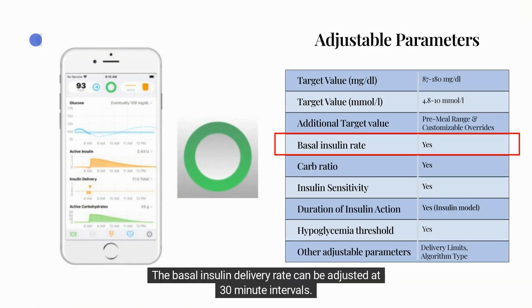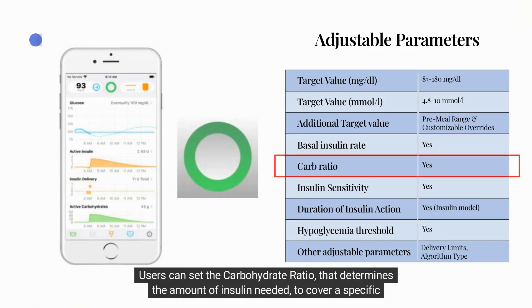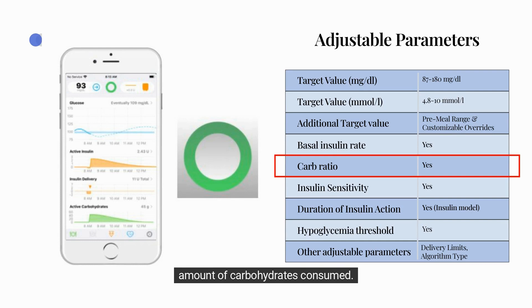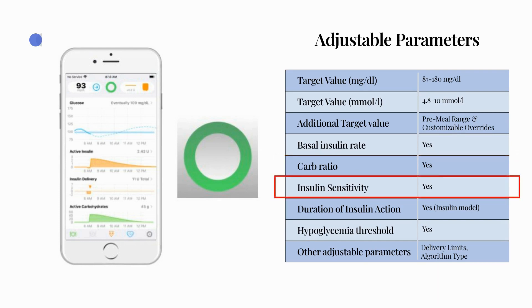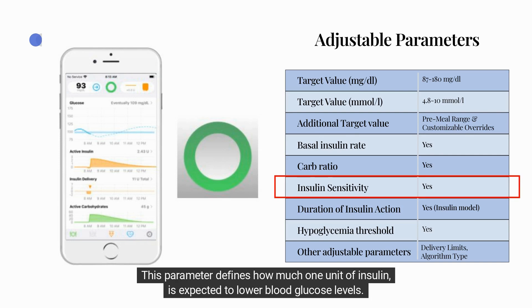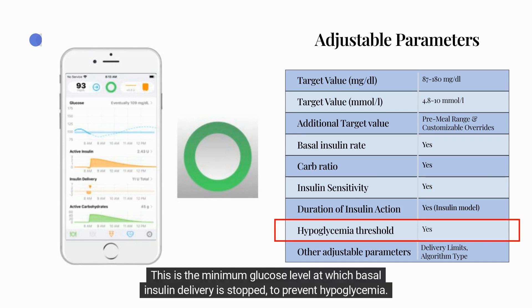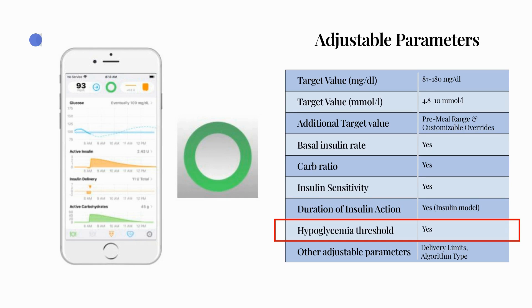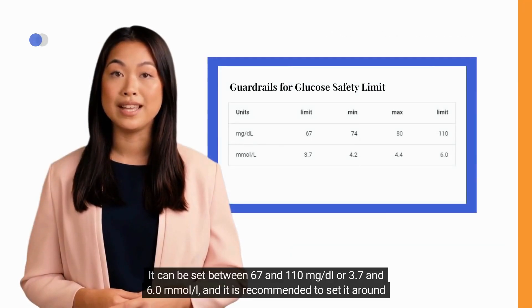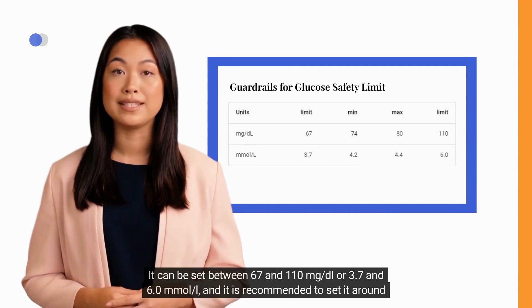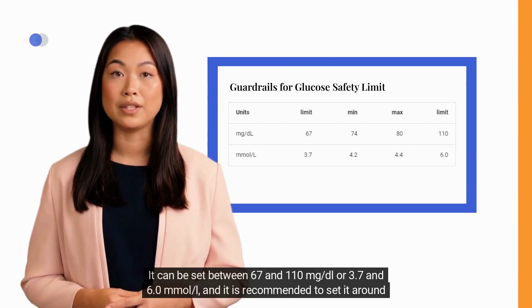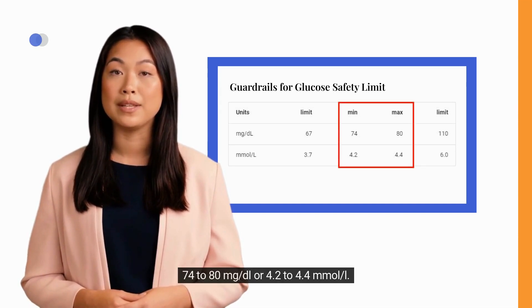The basal insulin delivery rate can be adjusted at 30-minute intervals. Users can set the carbohydrate ratio, which determines the amount of insulin needed to cover a specific amount of carbohydrates consumed, and the insulin sensitivity factor, which defines how much one unit of insulin is expected to lower blood glucose levels. The glucose safety limit can also be adjusted — the minimum glucose level at which basal delivery stops to prevent hypoglycemia — recommended to be set around 74 to 80 mg/dL or 4.2 to 4.4 mmol/L.